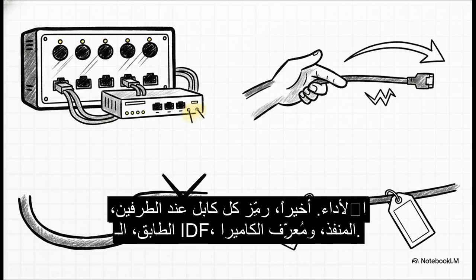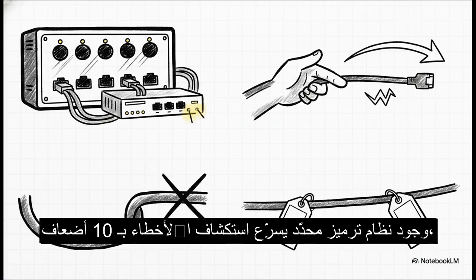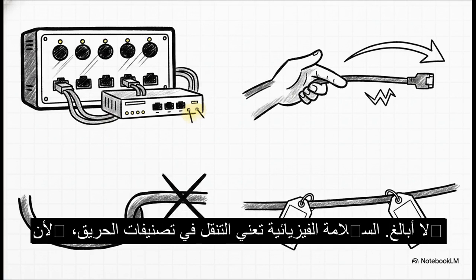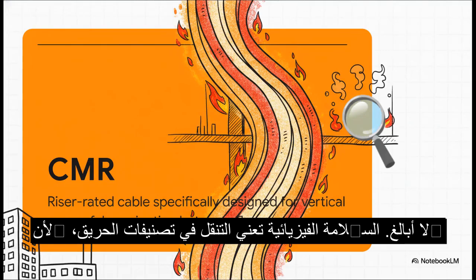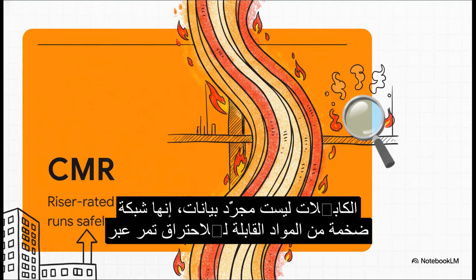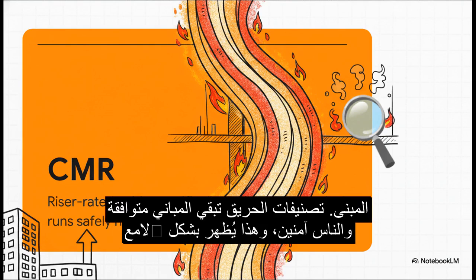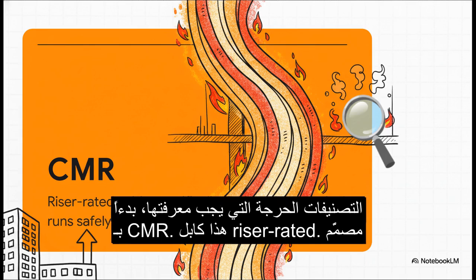Finally, label every single cable at both ends: floor, IDF, port, and camera ID. Having this labeling scheme mapped out speeds up troubleshooting by literally 10 times. I'm not exaggerating. Physical safety means navigating fire ratings, because cabling isn't just about data, it's a massive network of combustible material running right through a building.